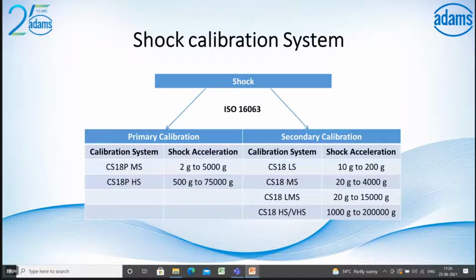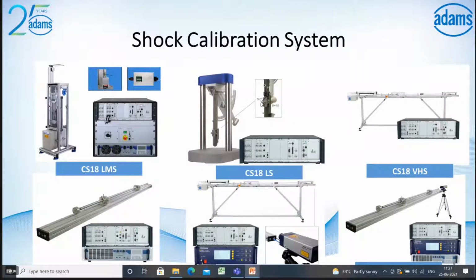And the secondary calibration systems. The CS18LS, that's a low shock, goes from 10 G up to 200 G at maximum. The CS18MS, that's a medium shock, goes up to 4000 G. The CS18LMS, that's a low medium shock, goes up to 15,000 G. And the CS18HS and VHS go up to 2 lakh G. So the CS18LMS, CS18LS and CS18VHS, this is how the system looks.